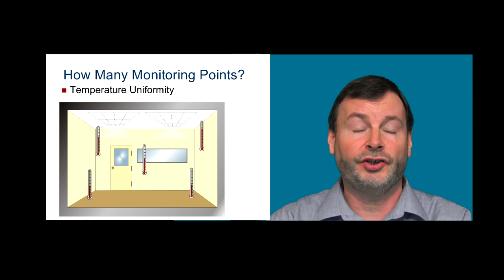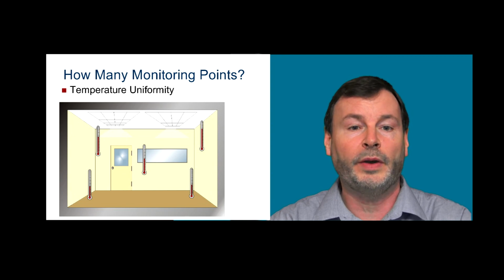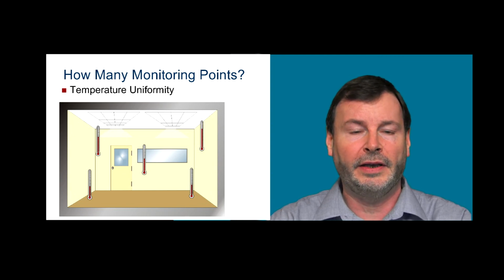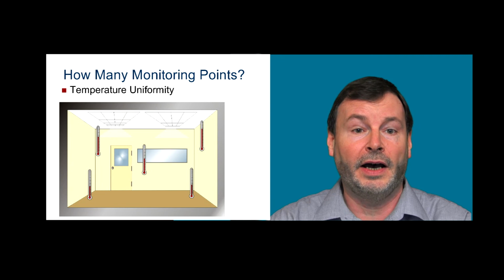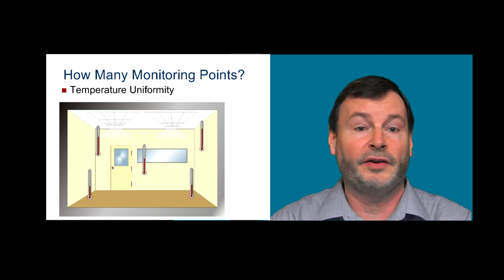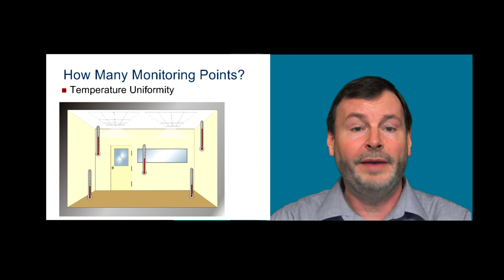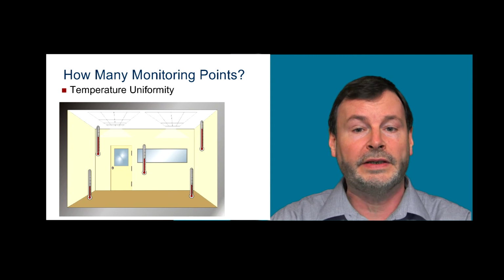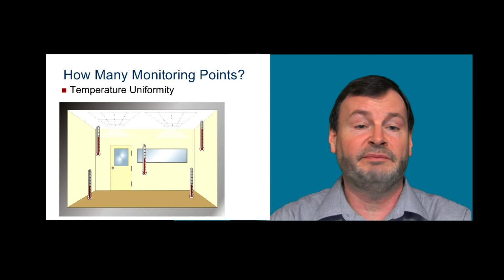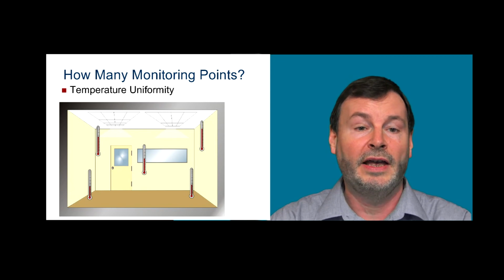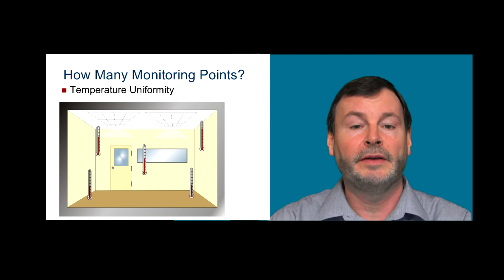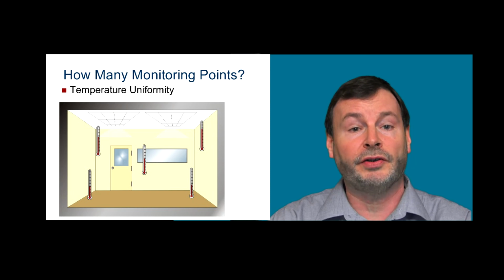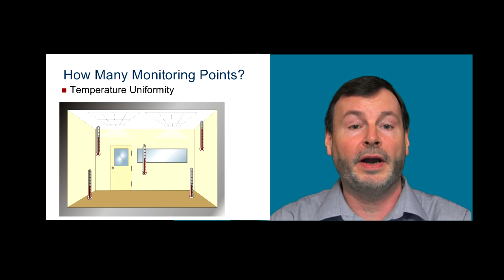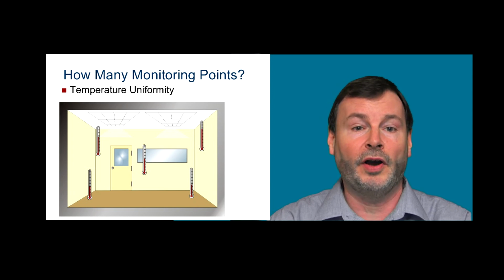Now additionally, we would get changes that are seasonal, both between summer when we have cooling coming in or in winter when we have heating. Now that means that if we need good measurement, let's say better than 10% in this particular room, we may need to have multiple monitoring points to truly understand what occurs in that room over time. If, on the other hand, we only need a 15 or 20% value, then probably a single point is adequate. But again, it's also important not to measure just the wall or the corners if we're trying to get a true representation of what's going on in the entire room.